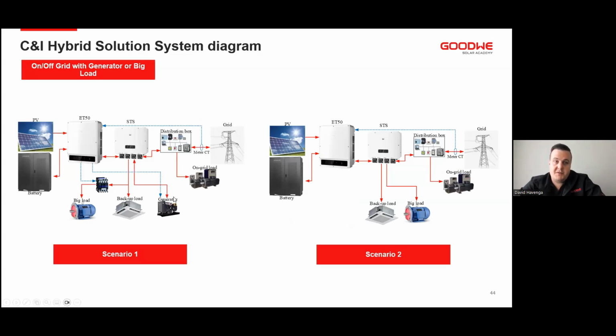Then we have other options, so on-grid or off-grid operations with a big load or generator. On the STS, we do have a generator port that you can use either for a diesel generator, or you can also set that to be used for a big load. Alternatively, the ET does have dry contact relays for load start and stop. So if we have larger loads, we can also put them on the backup side with an external contactor, just so that those loads don't exceed the inverter's capacity when the grid is off. Then we have that load contact relay to switch those loads in and out.